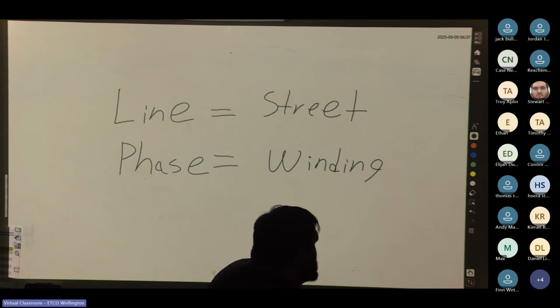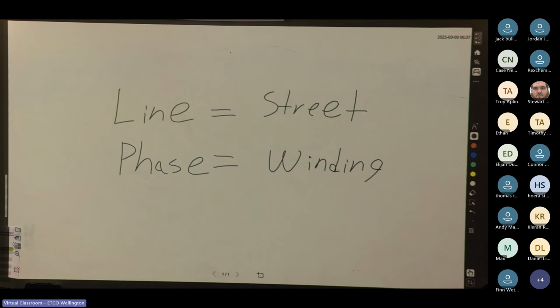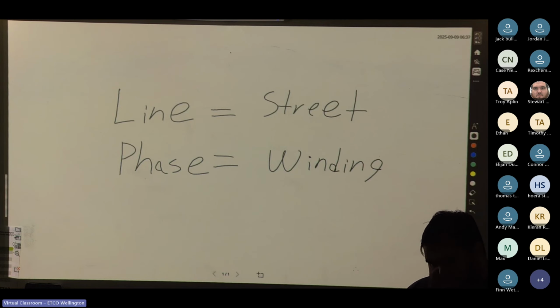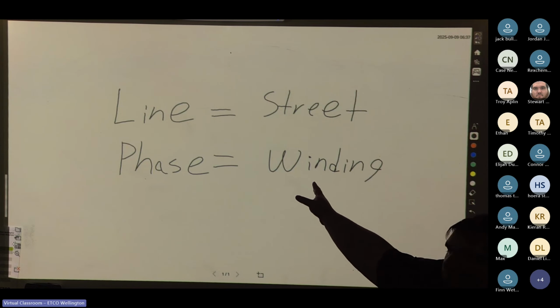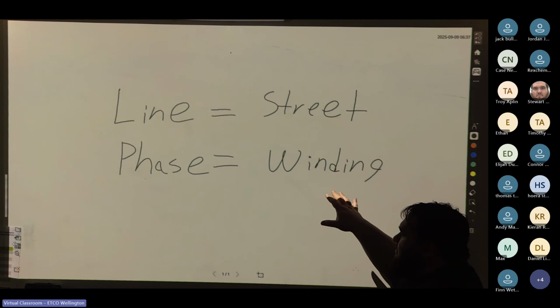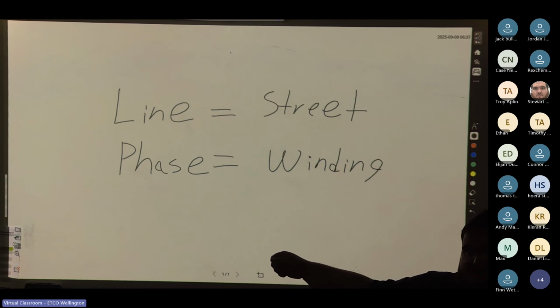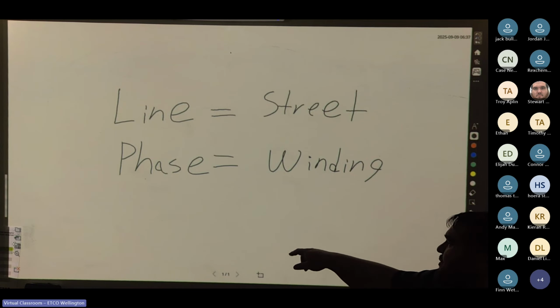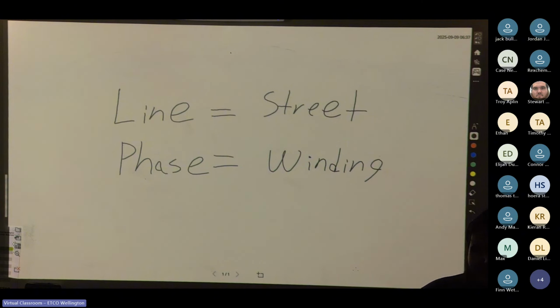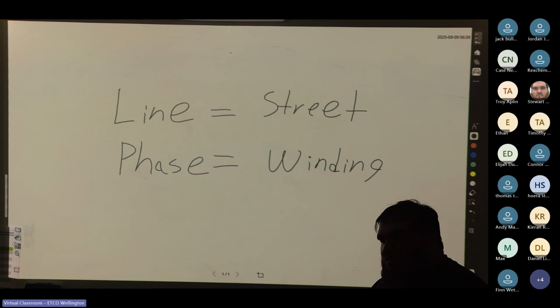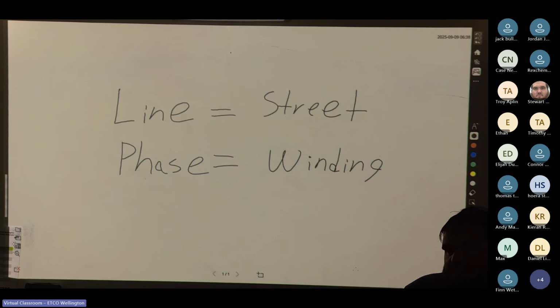So obviously, if we're measuring line voltage in delta or phase voltage, we're always measuring from either one end of the winding to the other, or between the connection points of each winding. So we're always going to get 400 volts in delta, because no matter what, we're always measuring the line voltage. Whereas in star, the line voltage is between phases, so we're measuring the lines. Whereas phase, we're measuring from one end of the winding to the neutral. So that's why we have the 230 volts. And I will explain that relationship in a little bit.